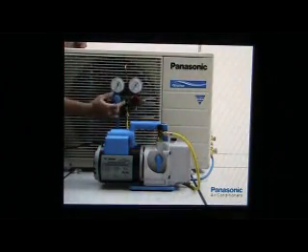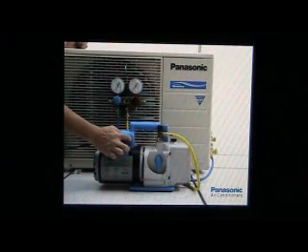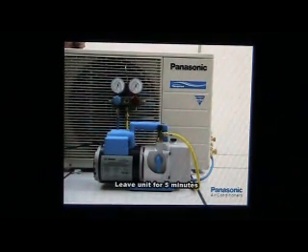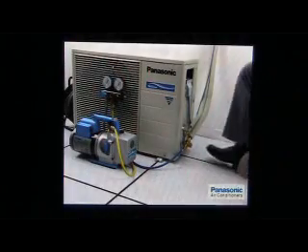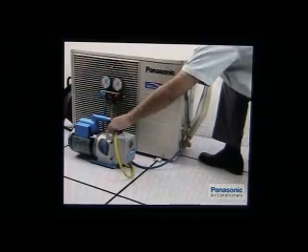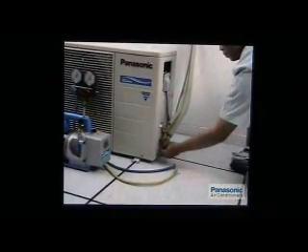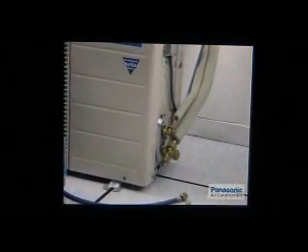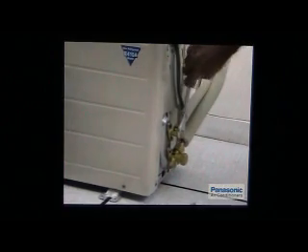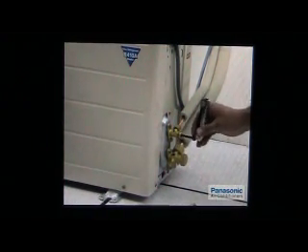When the evacuation is finished, close the low handle of the manifold gauge completely and turn off the vacuum pump. Leave the unit in that condition for 5 minutes to make sure the manifold gauge needle doesn't return to 0. Take note that if the needle returns to 0, there is a leak. Disconnect the charging hose from the vacuum pump and the service port of the three-way valve. Screw the valve stem cap to the service port using the torque wrench. Unscrew the two-way valve and three-way valve stem caps. Open the two-way valve by turning the valve stem.